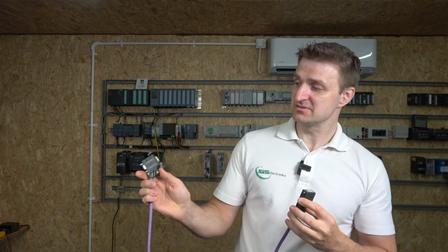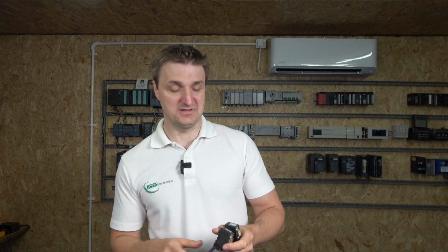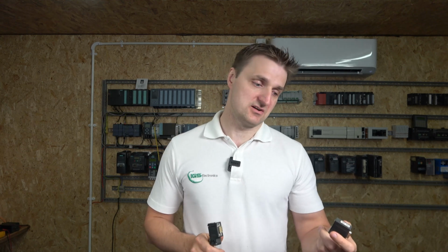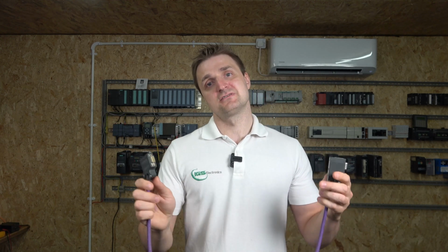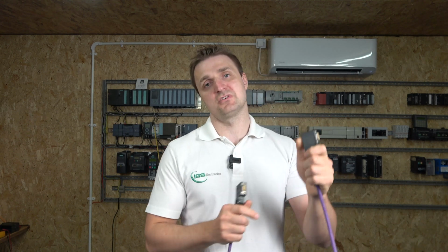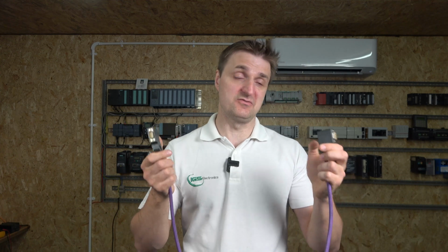Also, one more thing we're going to check is the switches here in the back. Those switches are called bus terminators. If you're going, like me, from one point to another point, the first device should always have the switch on, because that's the first device. If you're going to the next device and planning to spur off to another one, you need to push the switch into off, so it understands that the communication goes further than that point. So don't forget to do that if you're using more than two devices. We are going from one point to another point, so both ends will be on.